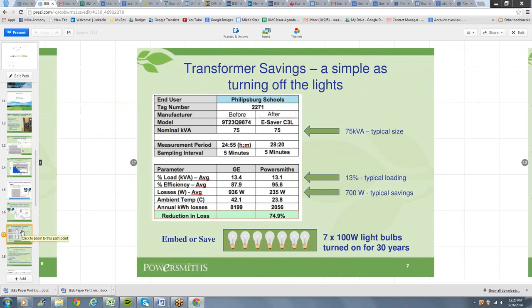I've taken a transformer before and after from a school location here, and it's a 75 kVA transformer, a very typical transformer size. As you can see, going to the second line, we're talking about a 13% average load, so we're in that typical light loading range. Going down to the next line, 936 watts before, 235 watts afterwards, so a 700 watt reduction. So, very typical of what you find: almost a kilowatt of losses for a 75, cutting it down to a couple hundred or so. So you say, there's your opportunity for savings.